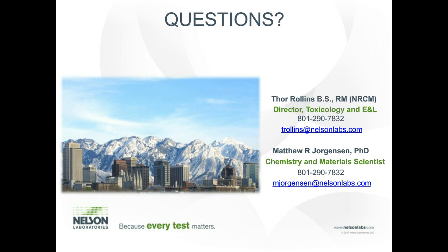Matt's not a big fan of FTIR, but FTIR may be able to help you evaluate some material similarities, especially compared to maybe some USP grade materials. But leachables will be able to help you identify if there are any changes with what compounds leach off those plastics. We really need to get away from saying, I got silicone from this vendor, now I got it from this vendor, it's still silicone, so I'm not changing my device. There are differences between them.